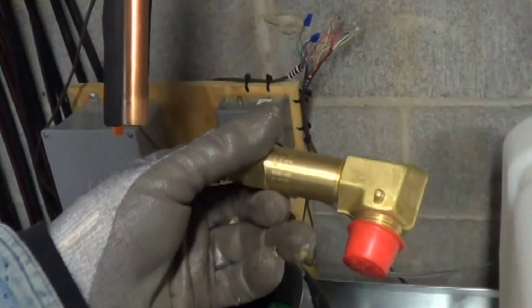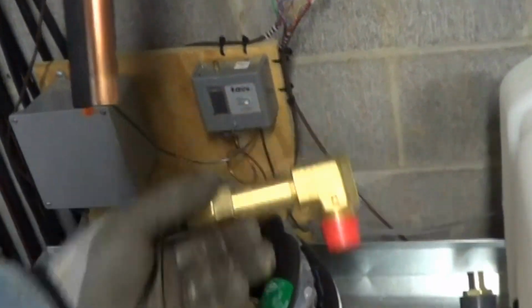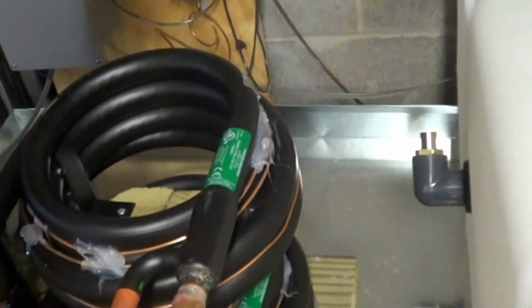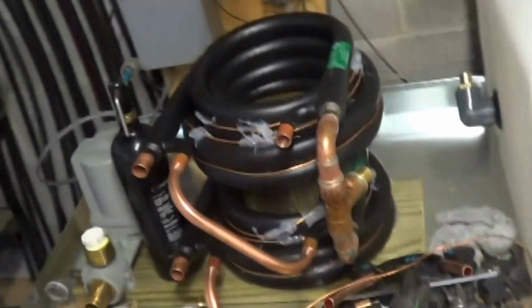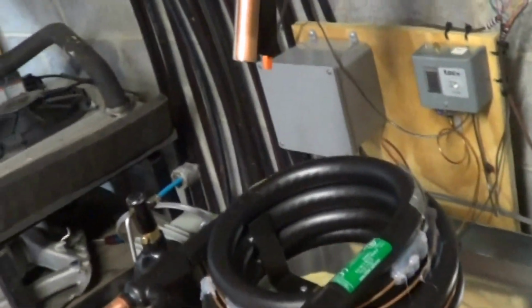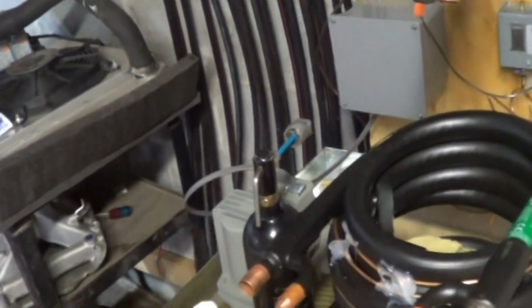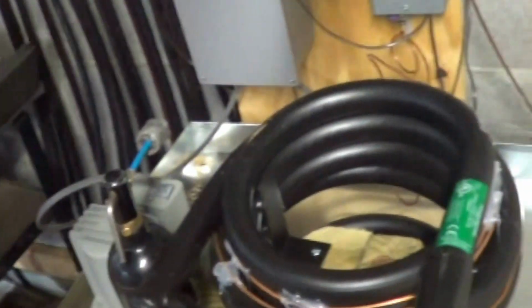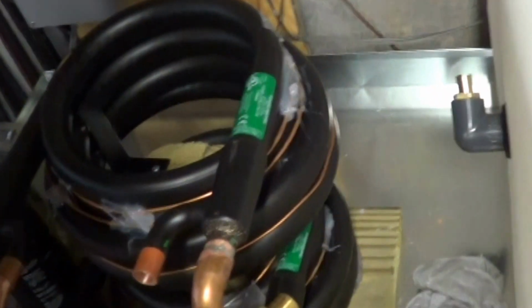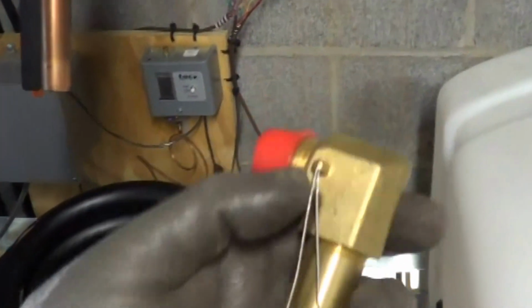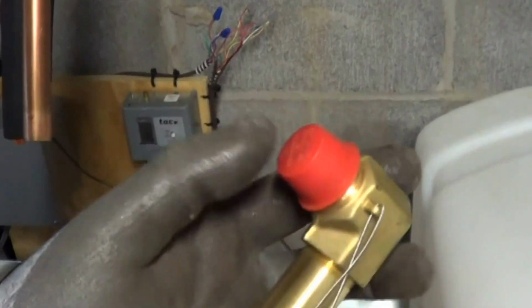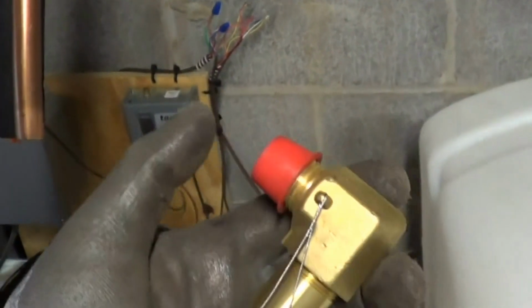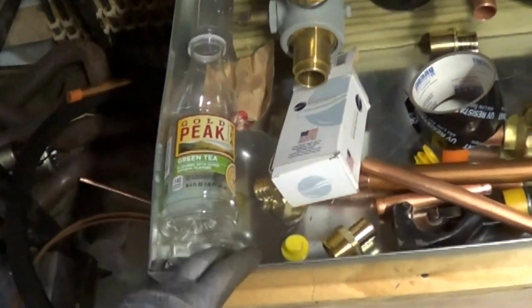Put some 600 psi pressure reliefs. So that makes it pretty foolproof, where if it's not pumped down properly and then it's left to get warm, it'll just pop a relief valve. And of course there's pressure safeties, high pressure safeties. So the pressure relief should never pop. You leave the cap on there to tell if it did pop, because it'll blow the cap off. And you can see I built a table. Got myself a little pan. So if we got any water leaks, right there.